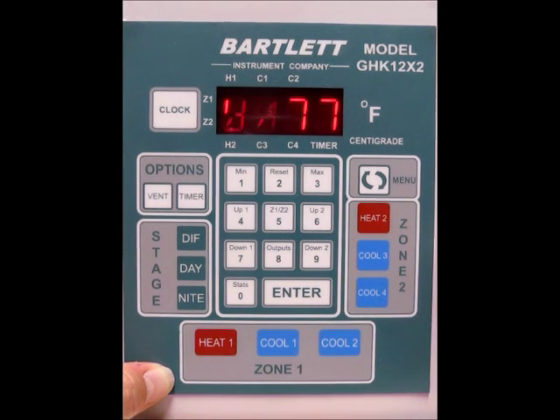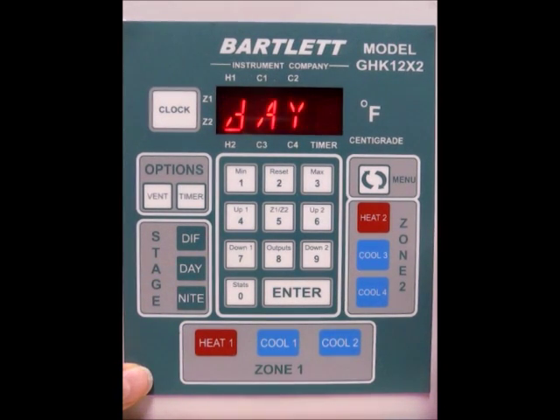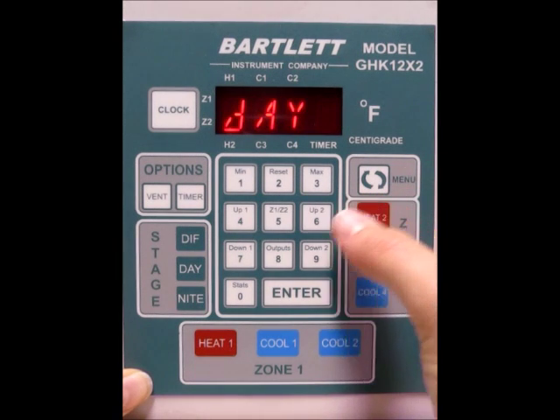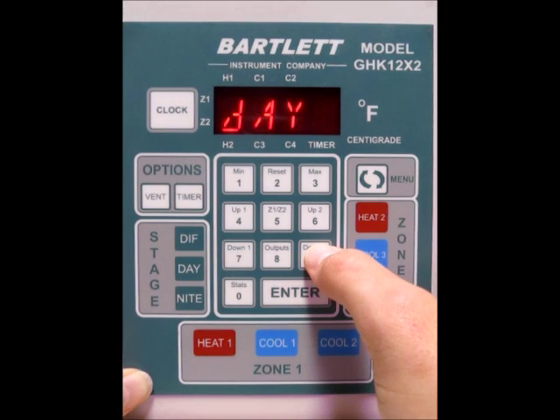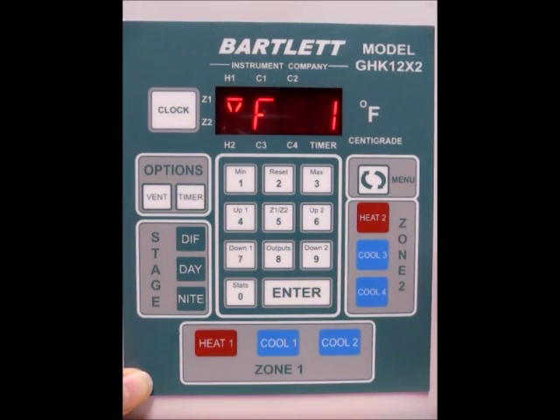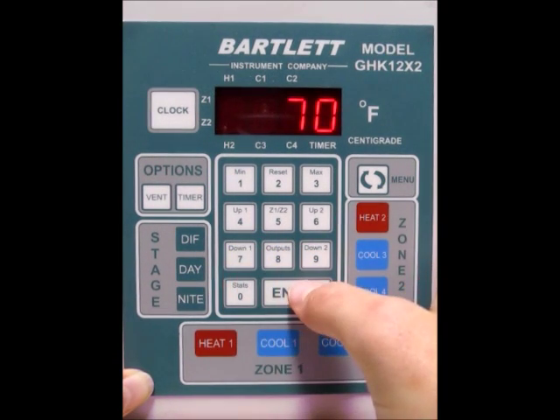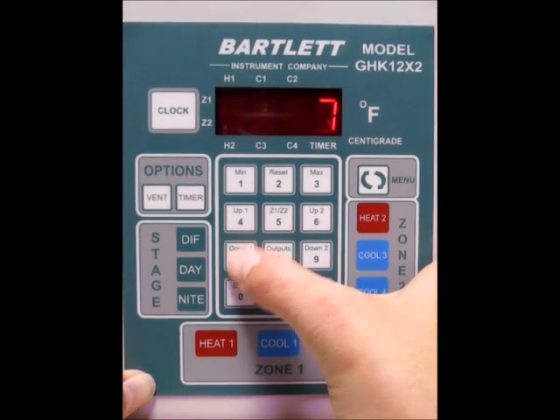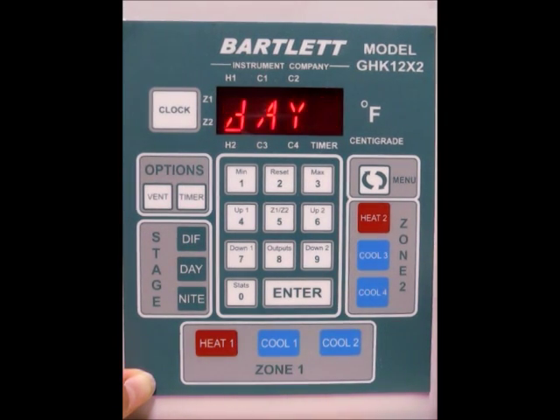Press the Day button. Right now Day is set to start at 8 a.m., so DIF would run from 6 to 8, but I'm going to change that to 9 a.m. Press 900 and press Enter. Now it's asking for your day temperature — set that to 70 and press Enter for zone 1. Then set zone 2 to 70 as well and press Enter. Now you're back to normal operating mode.